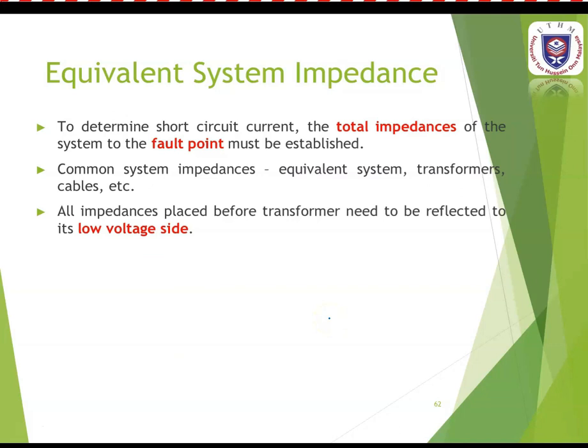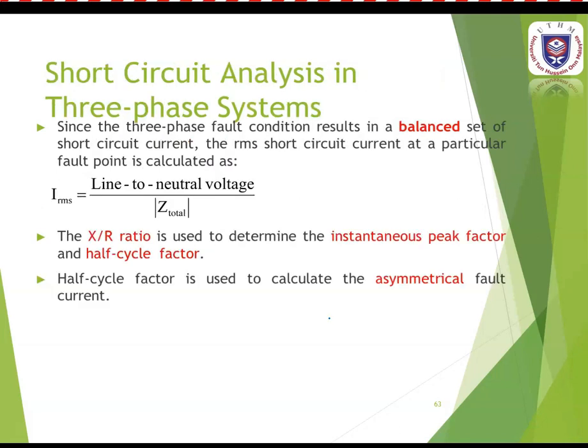To determine short circuit current, the total impedances of the system to the fault point must be established, same as voltage drop calculations. Common system impedances include the equivalent system impedance, transformer, and cable. All impedances placed before a transformer need to be reflected to its low voltage side. This is short circuit analysis in three-phase systems.